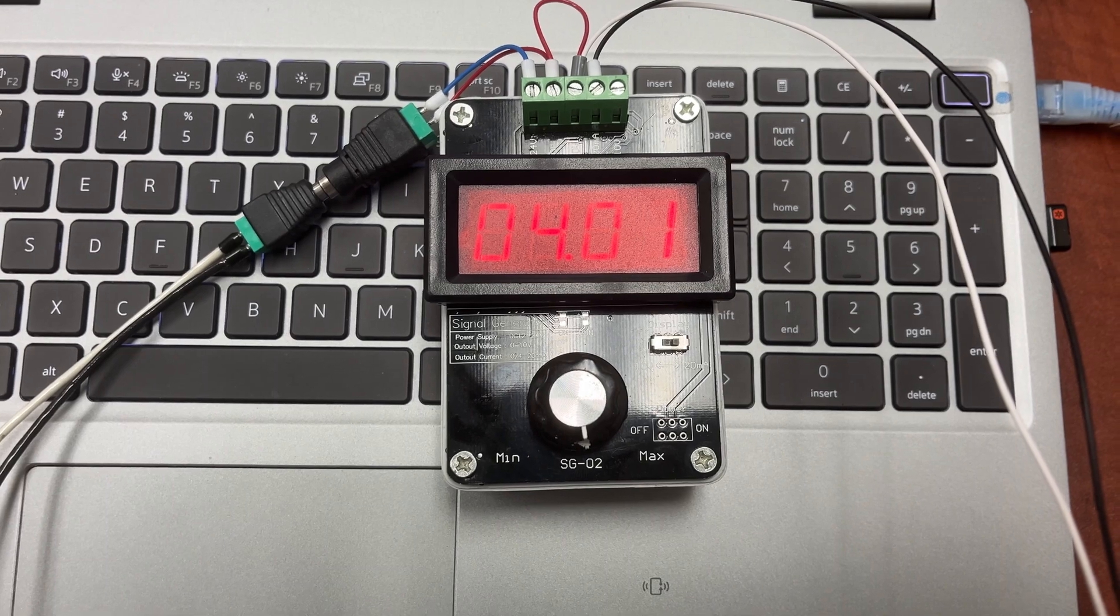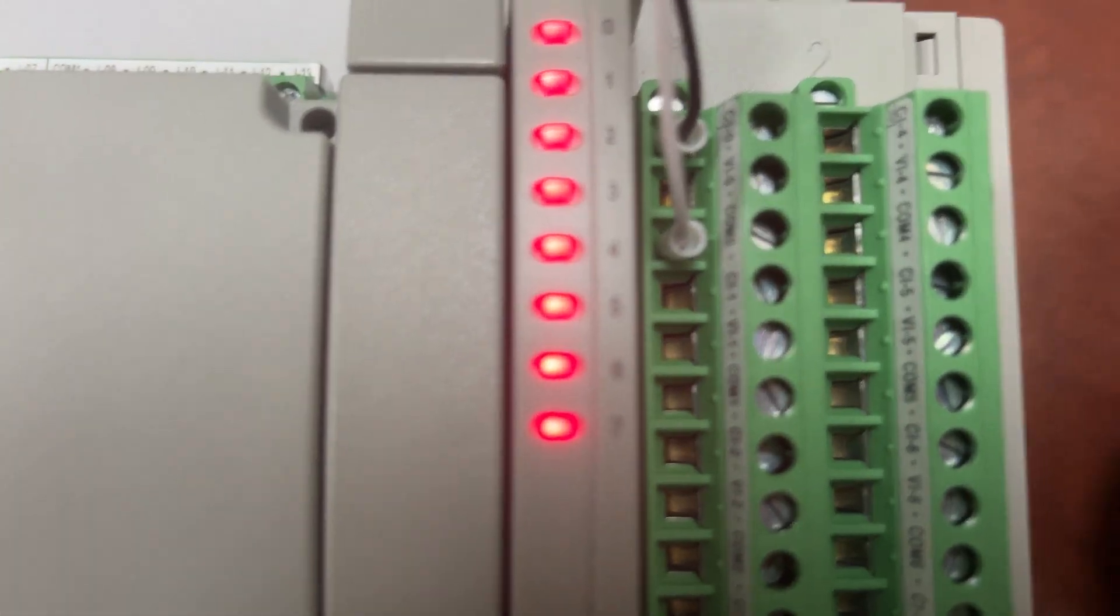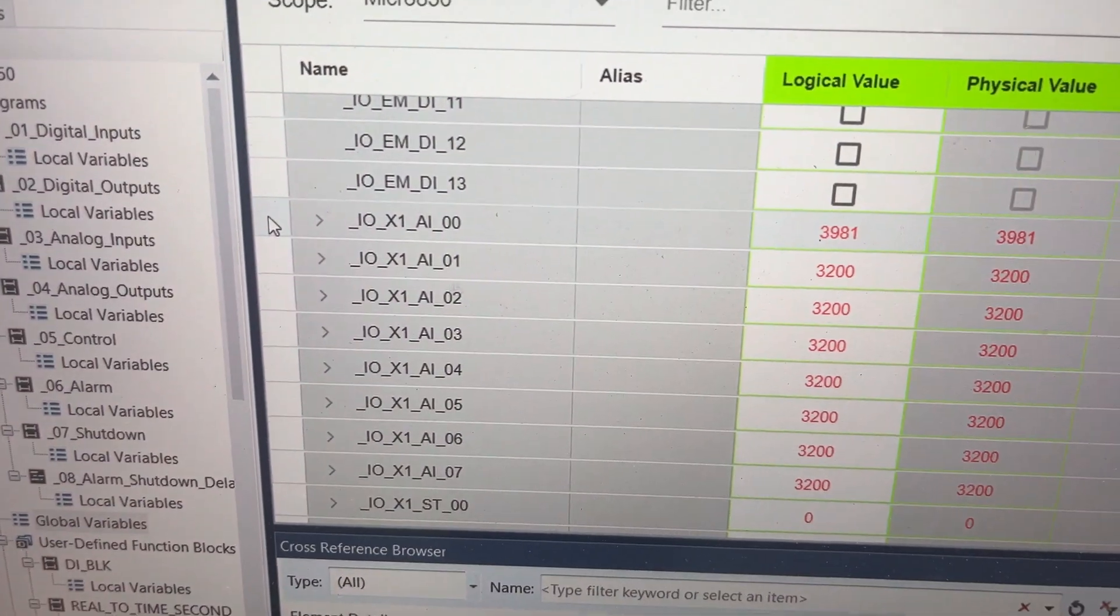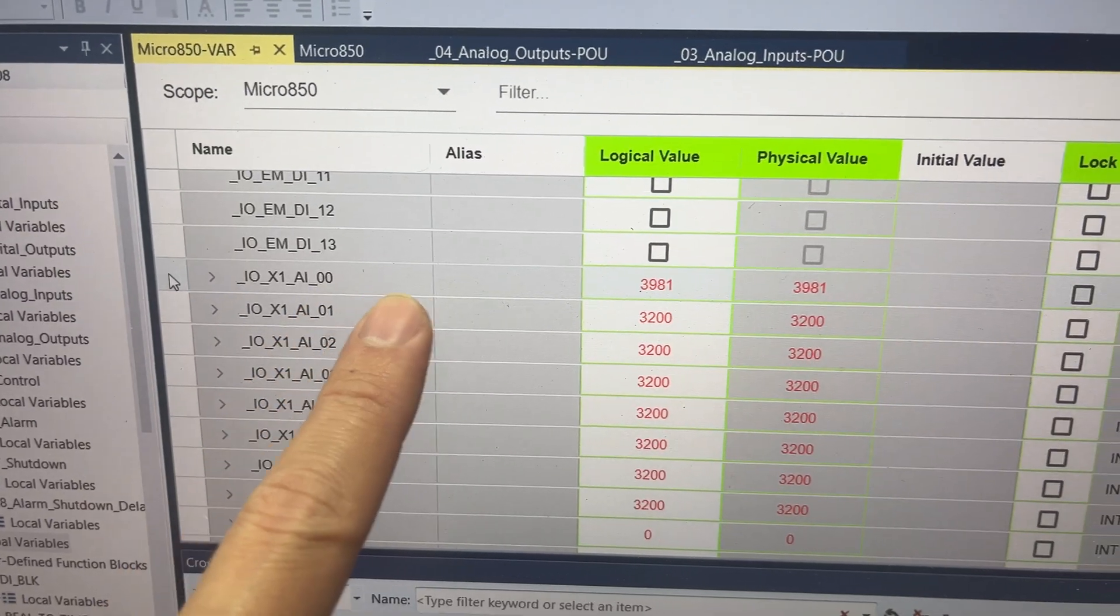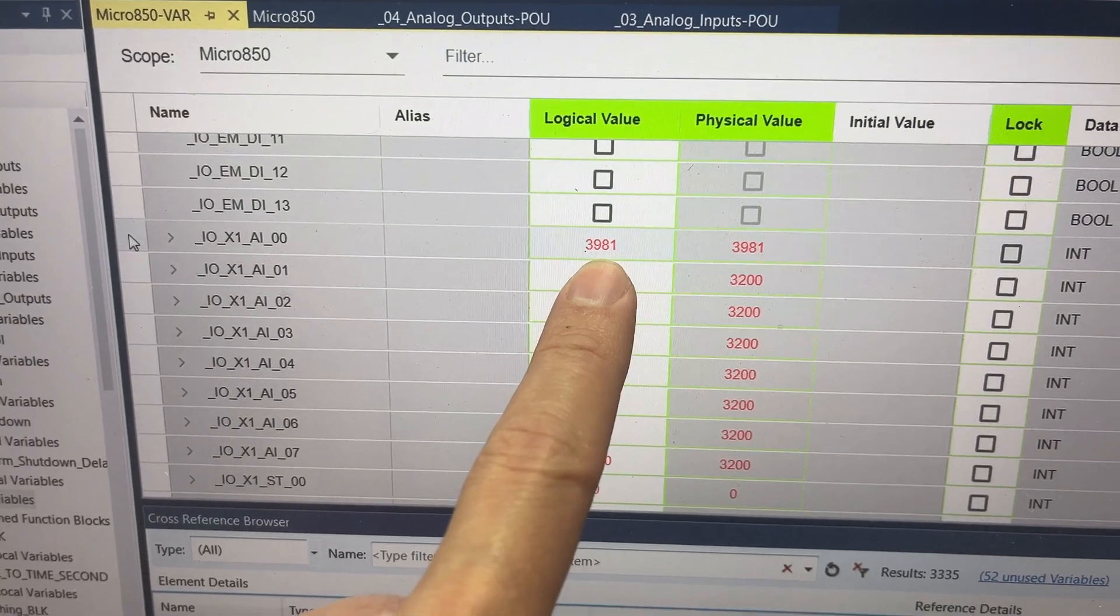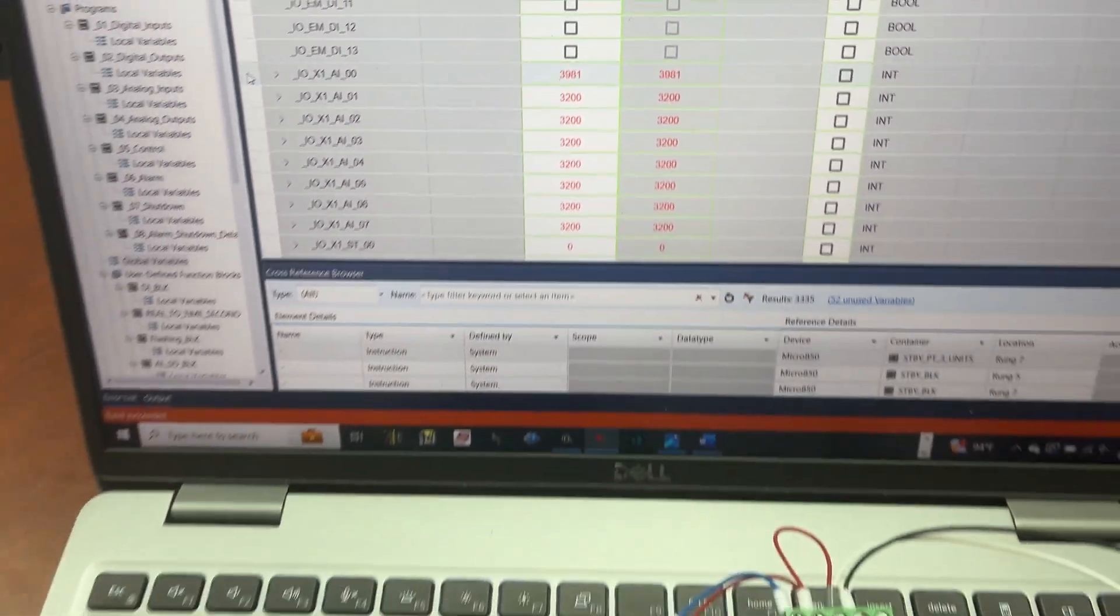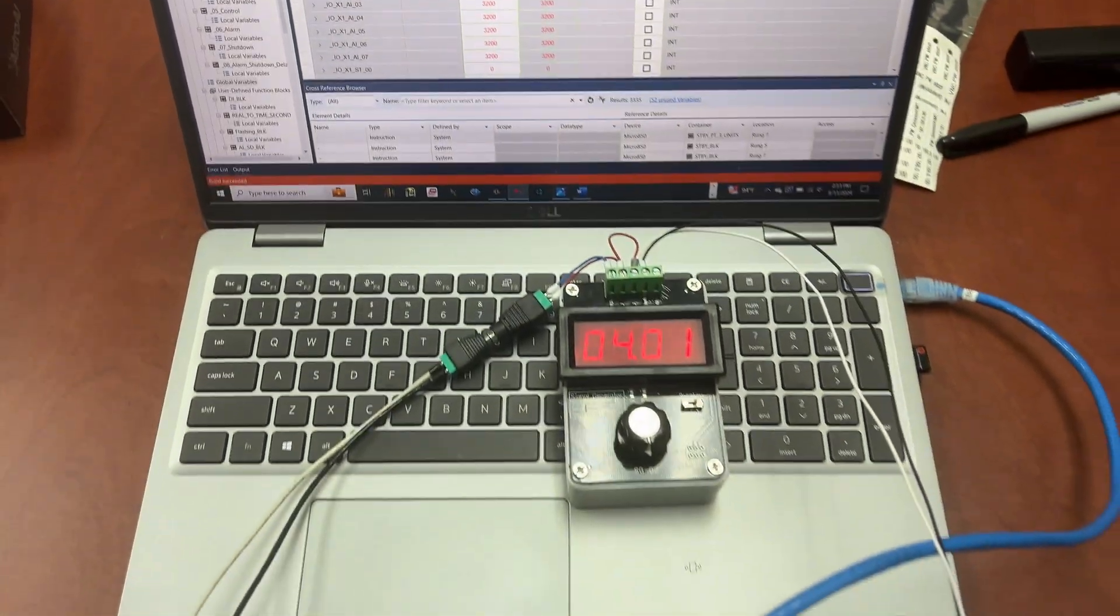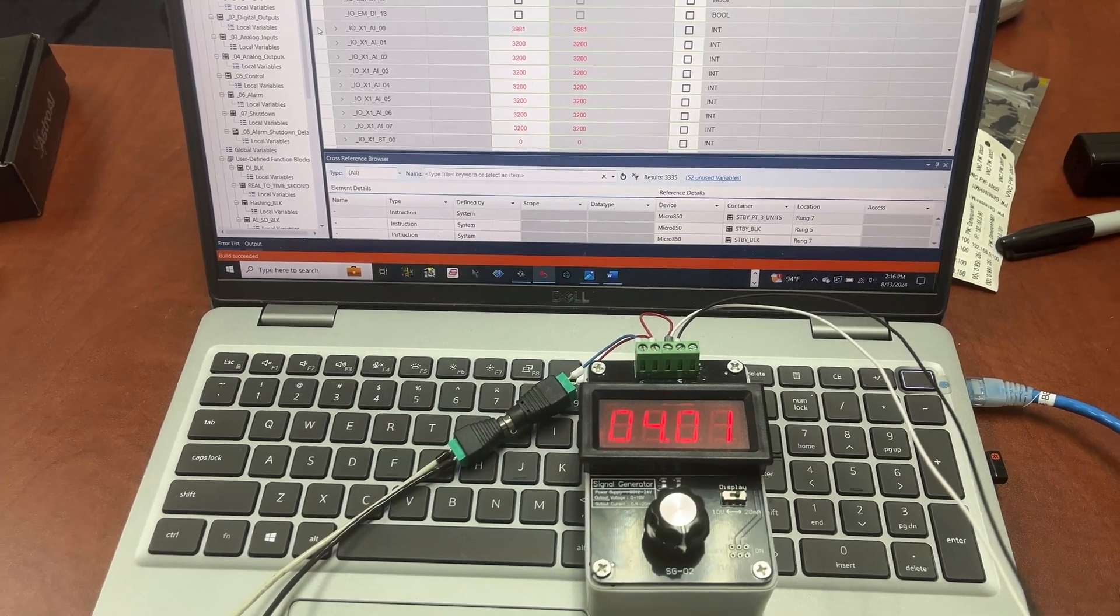For 4.01 milliamp signal to input channel 0 on the first expansion module, the PLC tag I-O X1 AI 00 will have the value of 3,981, very close to 4,000.